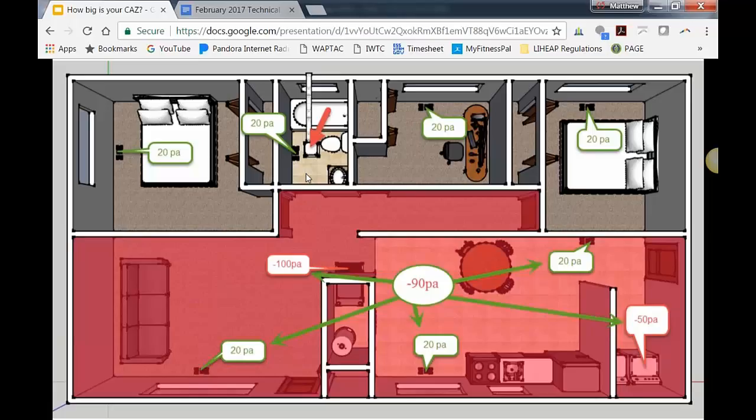But absolutely, it really should be tested at its highest flow rate, because the people living in this home could definitely walk in there and turn the fan on in the middle of the night and forget and leave it on, and they could close all of these doors, and they could be doing some laundry, and they could start dumping a bunch of CO in their house. We never know exactly what the homeowner is going to do, so within the controls or the things that they can affect, we try to turn all of those things on.